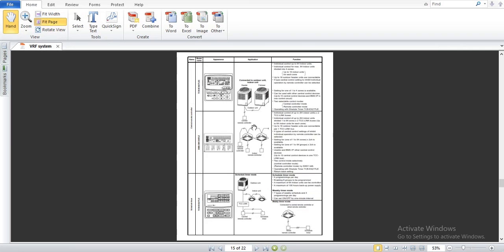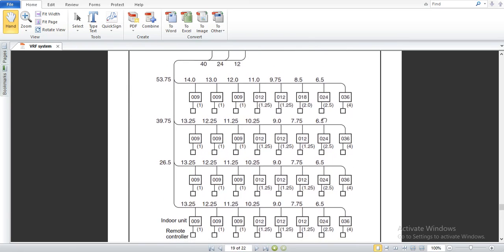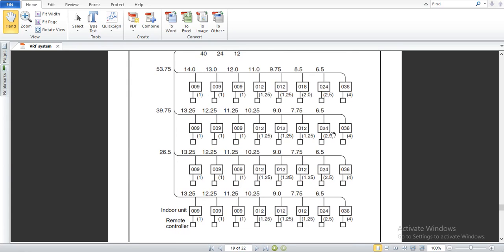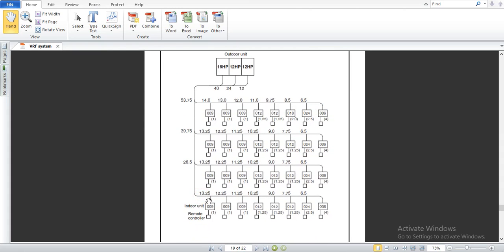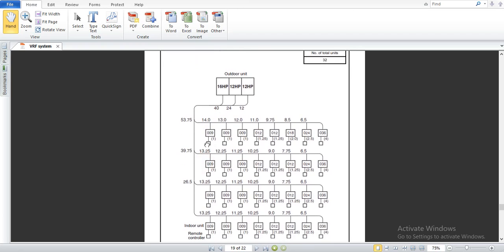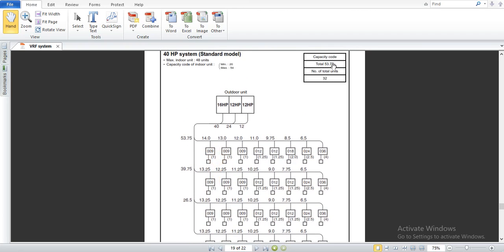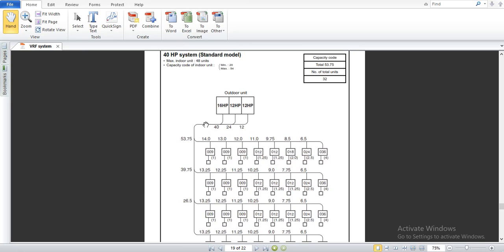Now I will explain one more example to make this clearer. In this example, we count the number of indoor units — there are 32 indoor units in our project. The capacity code, summing all indoor units, is 13.25 per group. So: 13.25 × 2 = 26.5, then 26.5 + 13.25 = 39.75, and 39.75 + 14 = 53.75. So the total capacity code of the indoor units is 53.75, and the number of indoor units is 32.